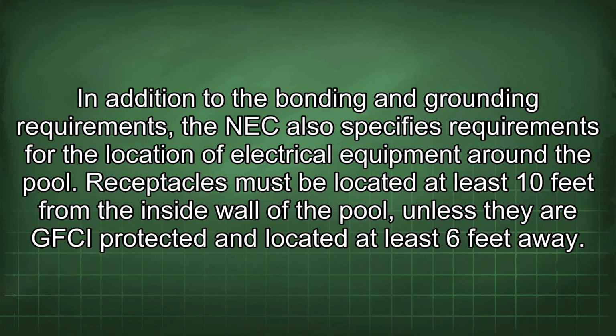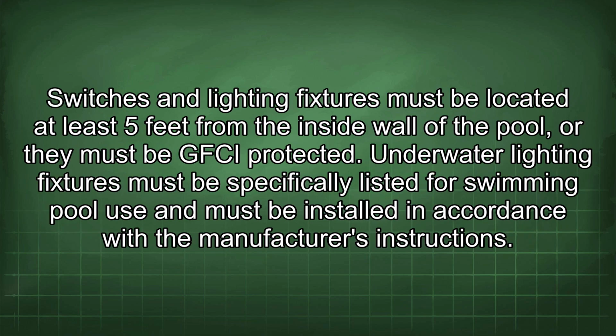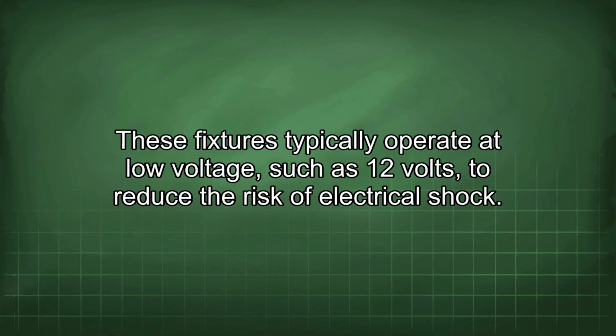In addition to the bonding and grounding requirements, the NEC also specifies requirements for the location of electrical equipment around the pool. Receptacles must be located at least 10 feet from the inside wall of the pool, unless they are GFCI protected and located at least 6 feet away. Switches and lighting fixtures must be located at least 5 feet from the inside wall of the pool, or they must be GFCI protected. Underwater lighting fixtures must be specifically listed for swimming pool use and must be installed in accordance with the manufacturer's instructions. These fixtures typically operate at low voltage, such as 12 volts, to reduce the risk of electrical shock.